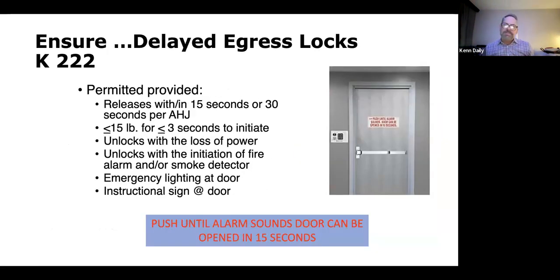Now, delayed egress doors, again, locking doors. The most common one is a 15-second delayed egress door, sometimes it's 30 seconds. The most basic requirement is that the door must be labeled appropriately with signage: push until alarm sounds, door can be opened in 15 seconds. It must be on the door, relatively in the middle of that door. The picture I have is probably a little bit high for that label. It can come down. There is no code requirement for the level. It just has to be on the door, and has to be of high contrast. So it just needs to be there. And then, of course, the function of the door is where you would actually push on that panic bar for 3 seconds or less.